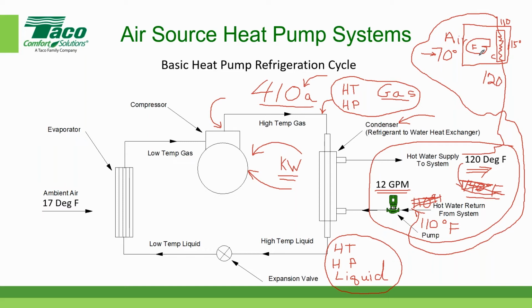But there are lots of new components available in the industry today that are specifically designed to run on low temperature entering water. So in our case, we're doing somewhere around 120 degrees. Remember, your space temperature in the wintertime wants to be around 68 to 70 degrees, so you have plenty of delta T to heat up your space. But you have to have enough surface area in your terminal unit to make use of that low temperature distribution.